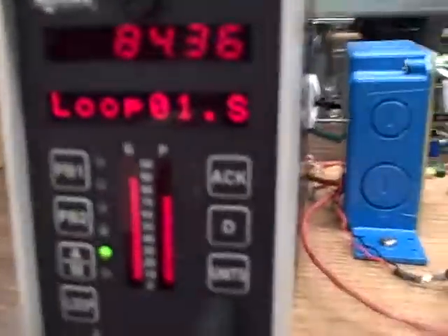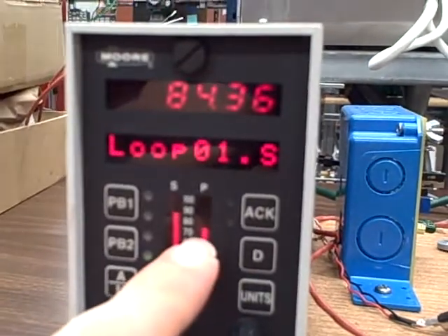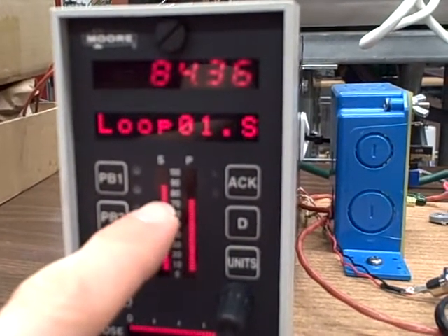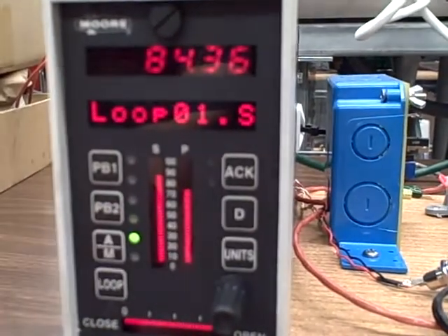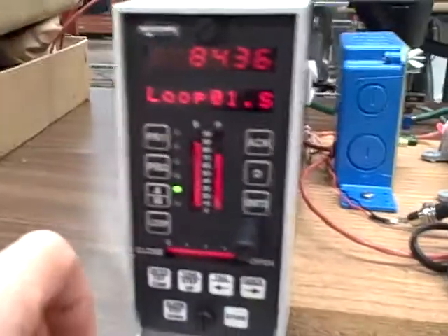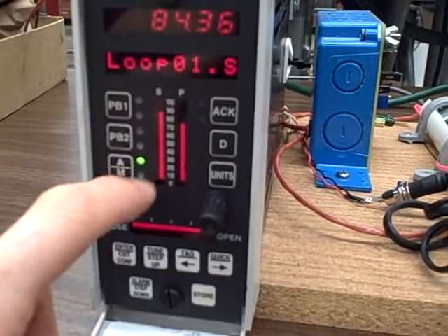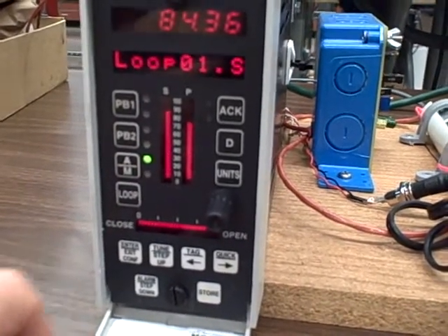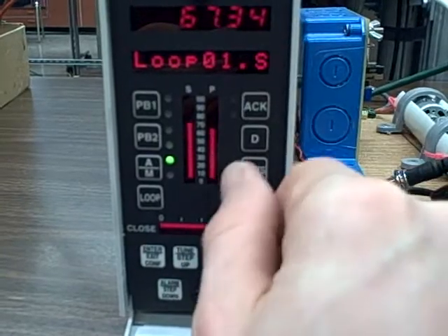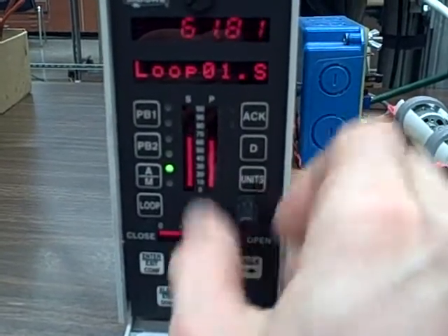But notice here on the process variable display, the process variable no longer equals the set point. We have an error that's developed, and this is also known as offset. If you have pure proportional control, you will always end up with an offset like this at certain points throughout the controlled range. I'll show you towards the bottom end of the range. I'll decrease the set point. We'll see the offset go away. Process variable and set point are becoming more and more equal to each other.